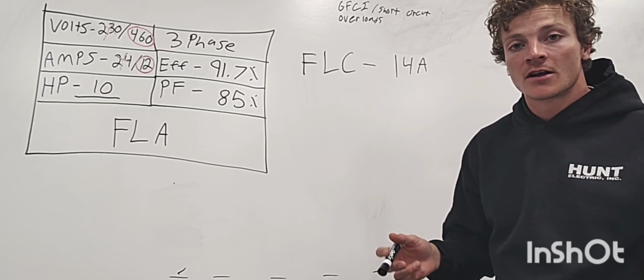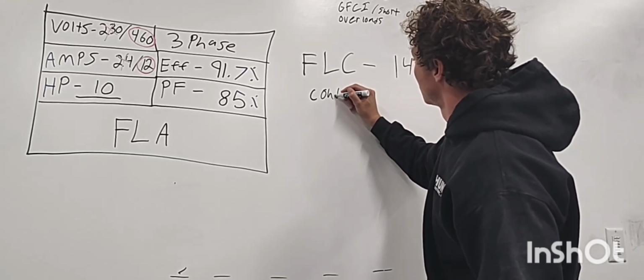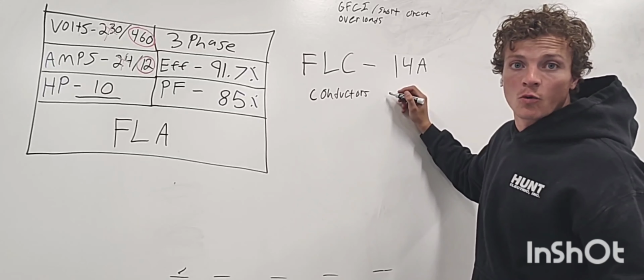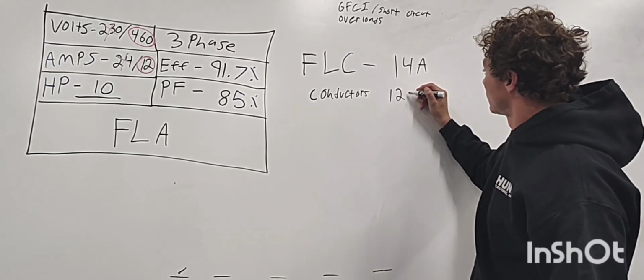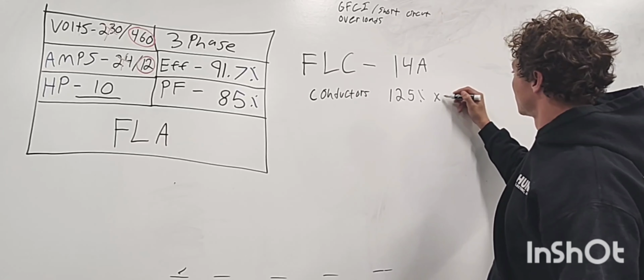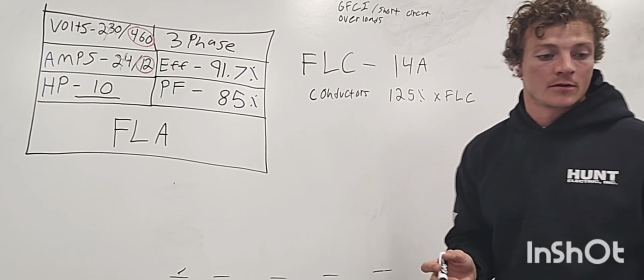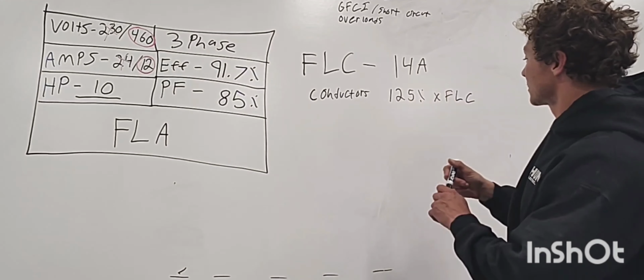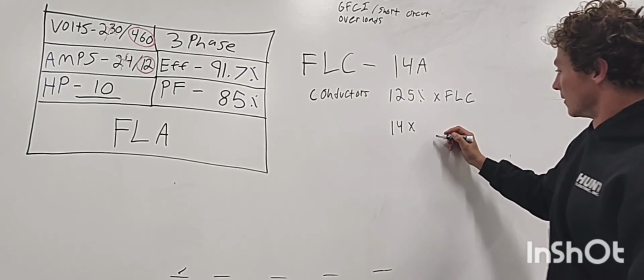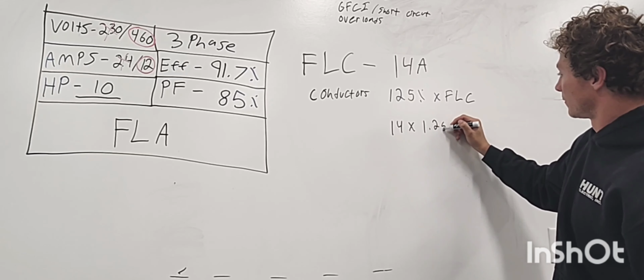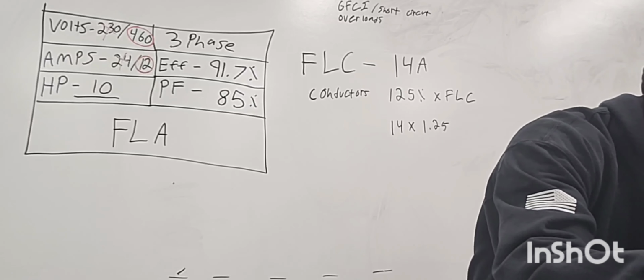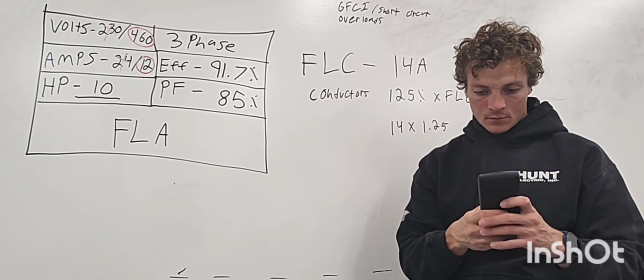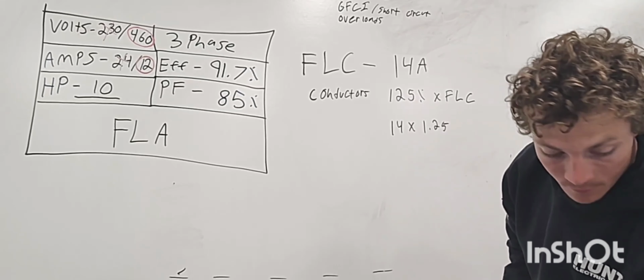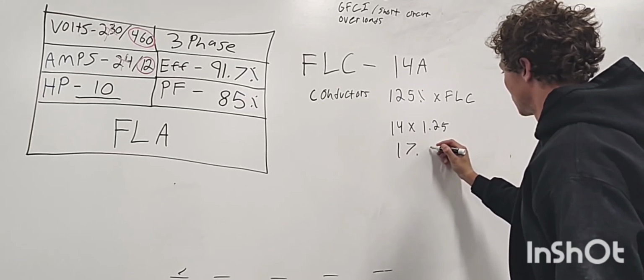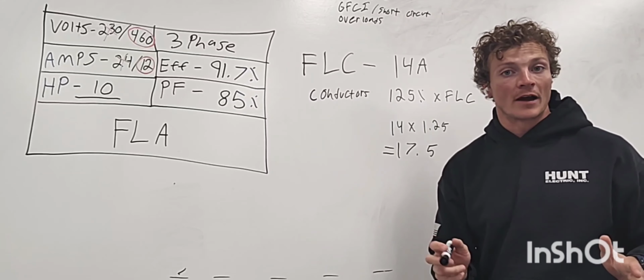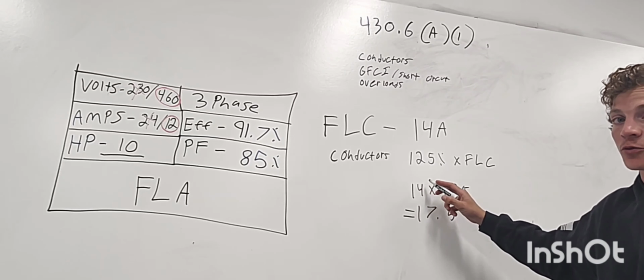Now, since we're sizing conductors, we need to remember conductors at 125% of the FLC. So what we're going to do is 14 amps, so 14 times 1.25. Let me get my calculator here. 17.5. 17.5 amps.